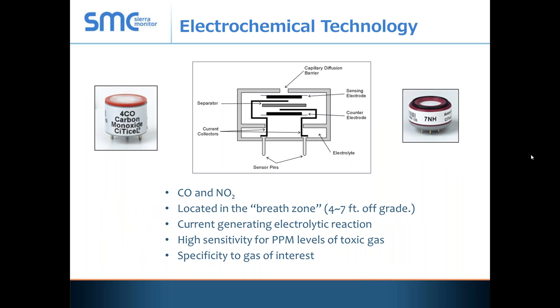The electrochemical technology is essentially an elaborate battery. As gases get in between the dielectric plates, the proportional voltage changes — that's how we measure them. These sensors are normally located in the breath zone, anywhere from 4 to 7 feet, and they measure in parts per million. So you won't see them measure in LEL.